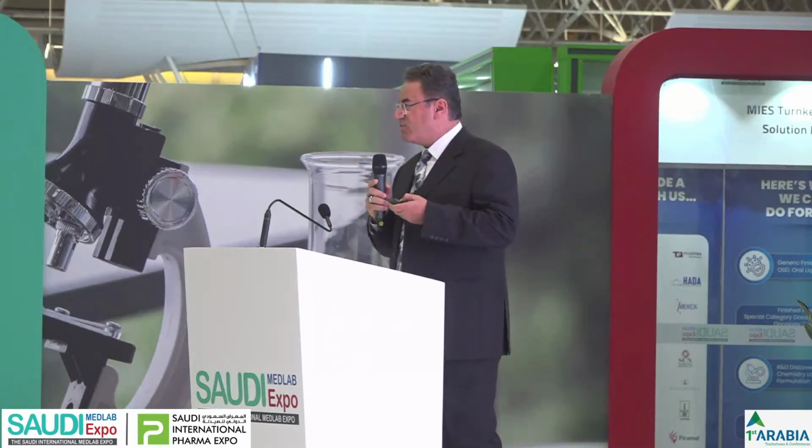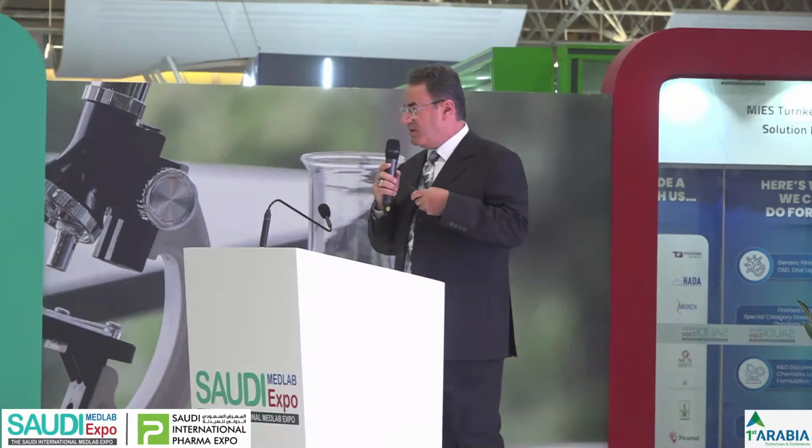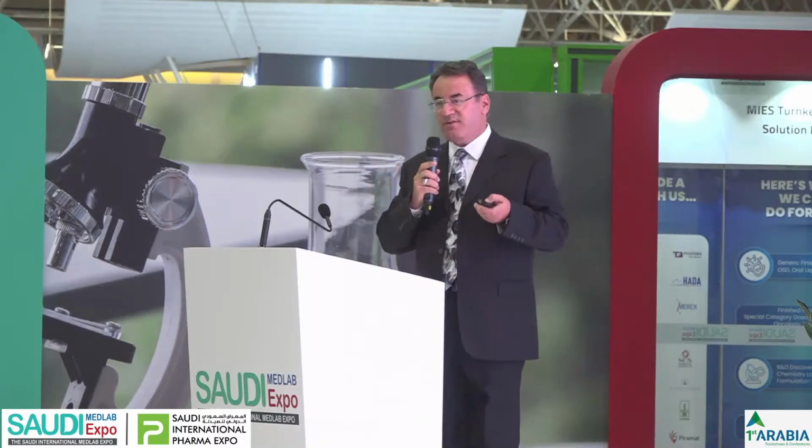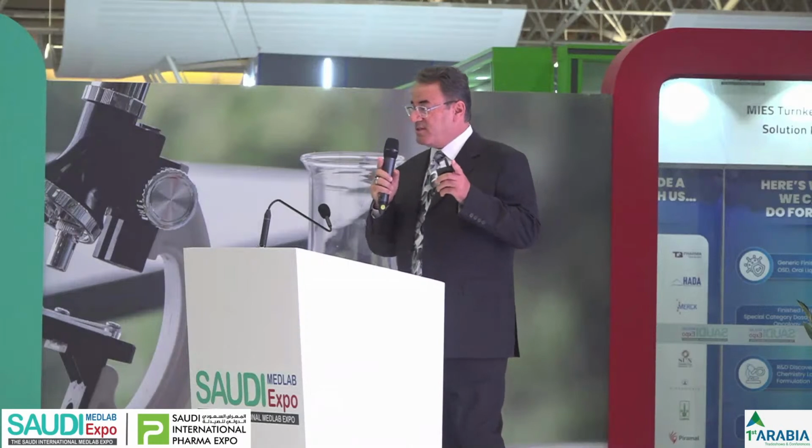The company just provides you with the material, whether it's blood or serum or plasma, and then you need to establish the ranges for each analyte. So now we know the difference between assayed and unassayed QC. Assayed comes with ranges, unassayed doesn't come with ranges.